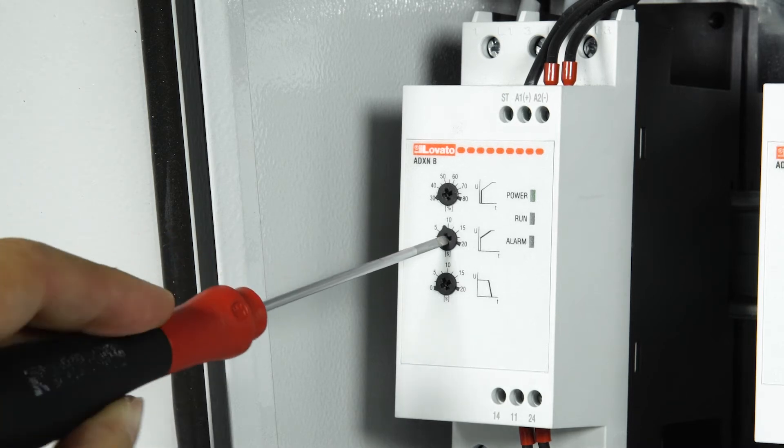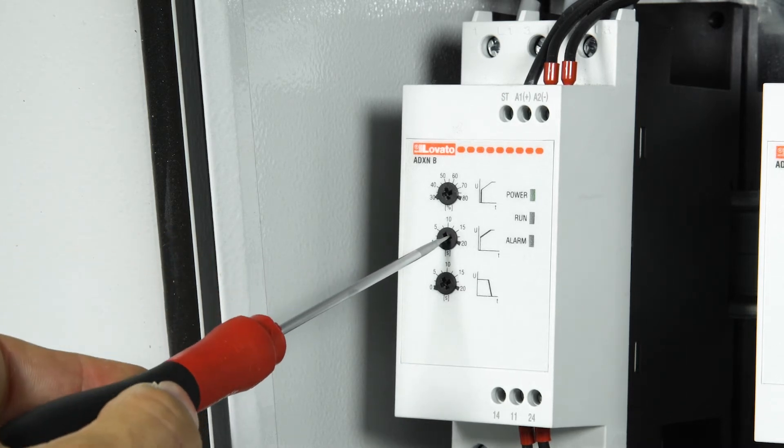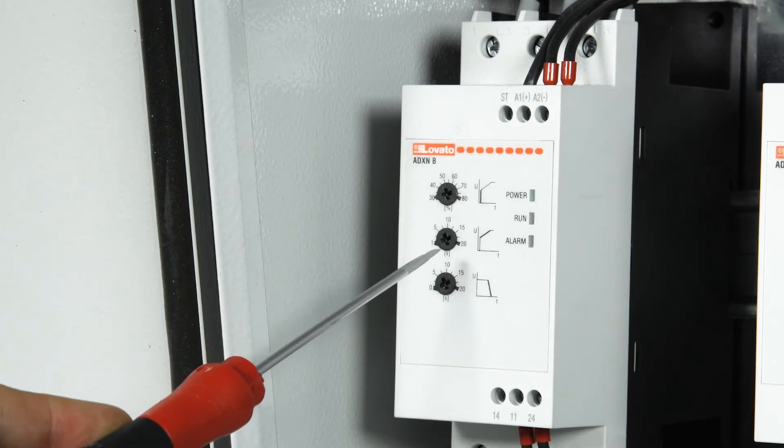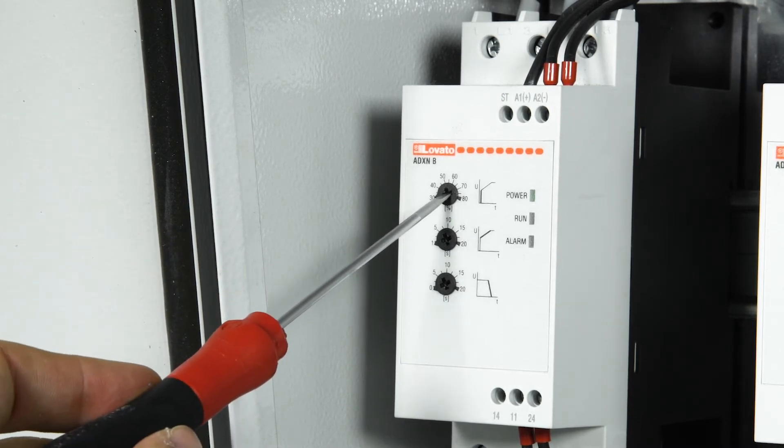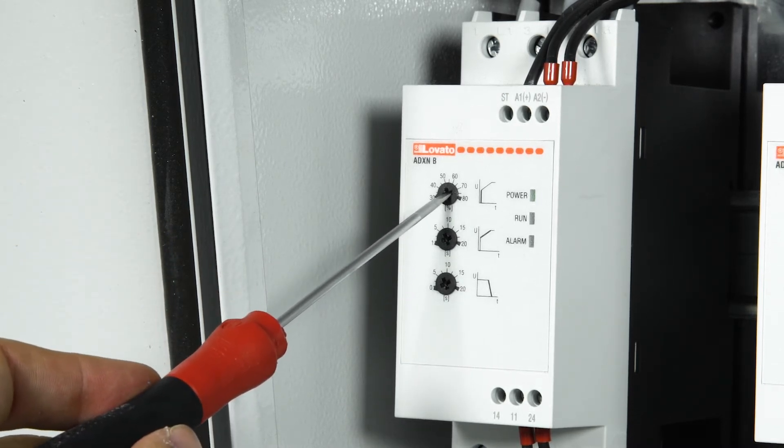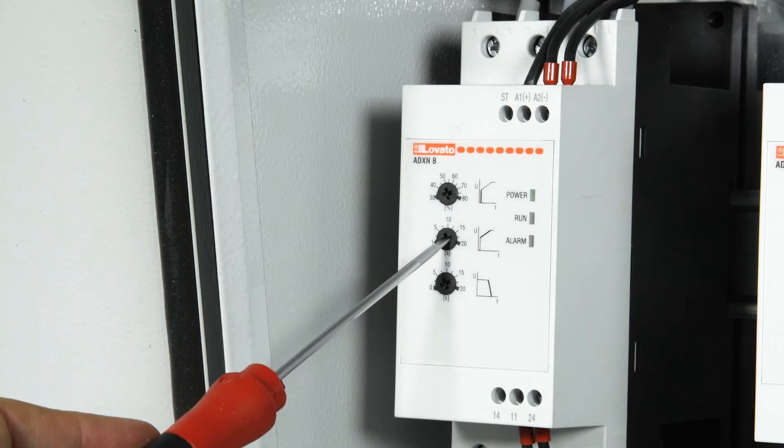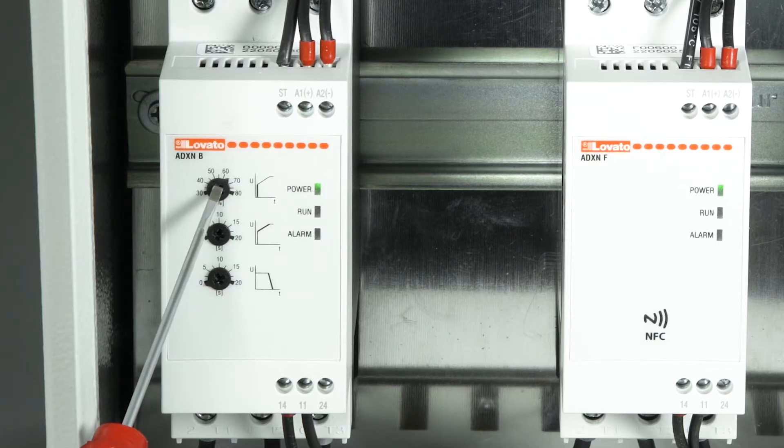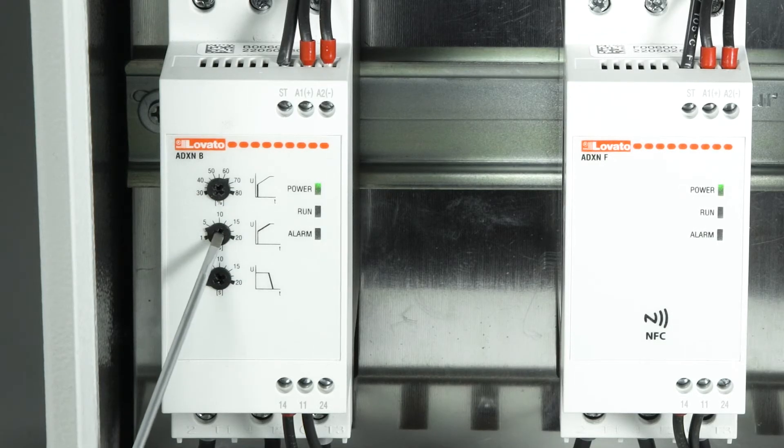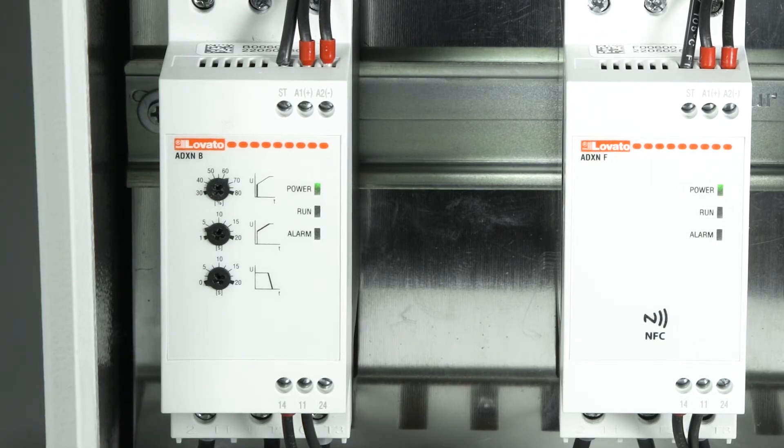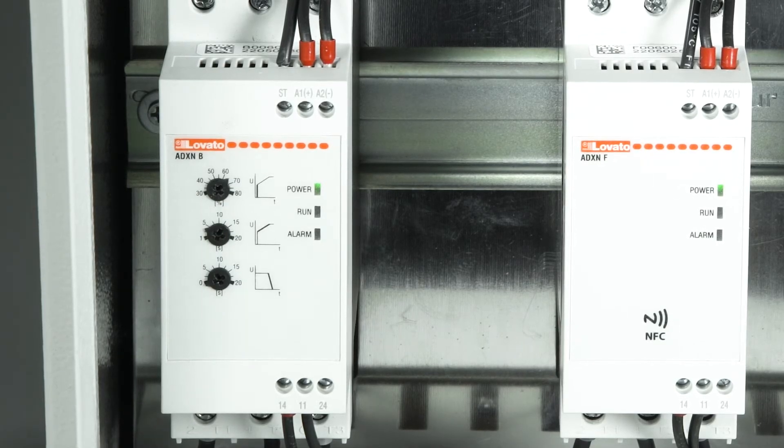The actual acceleration time also depends on the starting voltage set at the previous step. The higher the starting voltage, the shorter the effective ramp time will be to reach the full voltage.